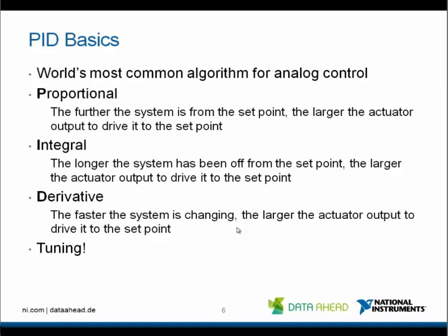The proportional part means that the further the system is from the set point, the larger the actuator output to drive it to the set point. The integral part means that the longer the system has been off from the set point, the larger the actuator output. And derivative means that the faster the system is changing, the larger the actuator output to drive it to the set point.